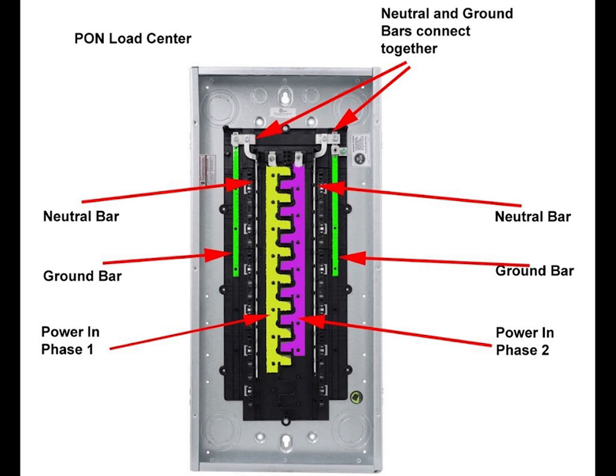The neutral bars. Each plug-on neutral load center has two neutral bars. The neutral connector on the circuit breaker attaches to the neutral bar. These neutral bars are attached to the ground bars at the top of the load center. The white neutral wires normally will connect through to the neutral bars.